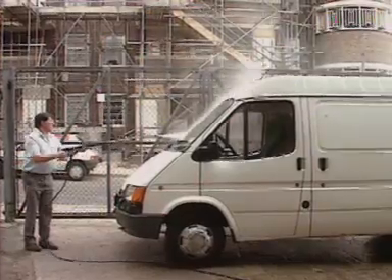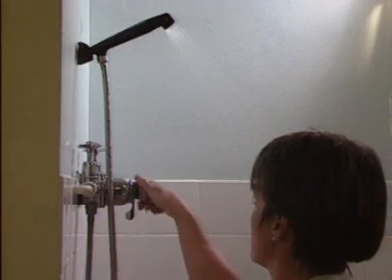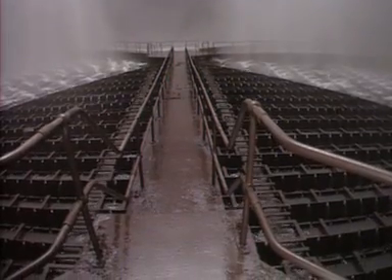Aerosols can be generated from water in a variety of ways. Simply turning on a tap may generate an aerosol — a shower, rainfall, or in the case of cooling towers, the distribution system, the spray, or the trough and gutter distribution system. An aerosol produces a range of droplet sizes. Larger ones fall to earth fairly rapidly, but smaller ones stay airborne and continue to evaporate down to an inhalable size that can cause infection.